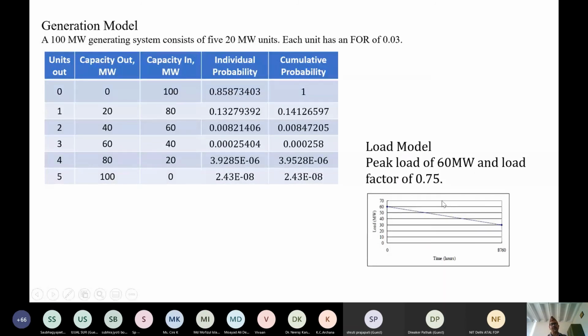And the load model is shown like this: peak load of 60 megawatt and load factor of 0.75. So 60 megawatt here and the lowest load will be 30 megawatt. So this gives us the 75% load factor. So if 60 megawatt was present all the time, the load factor would have been 1. Okay, so this would have gone in this way. So this one reduces the consumption by 25%. You can see. So that's why the load factor is 0.75 only.